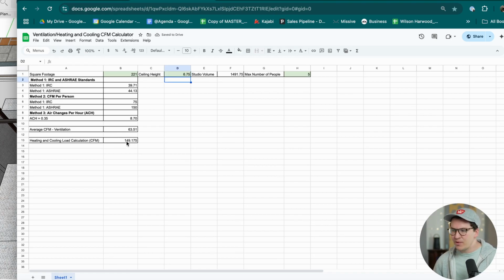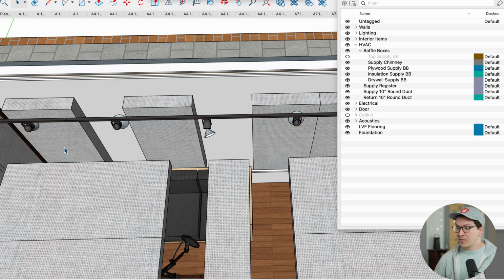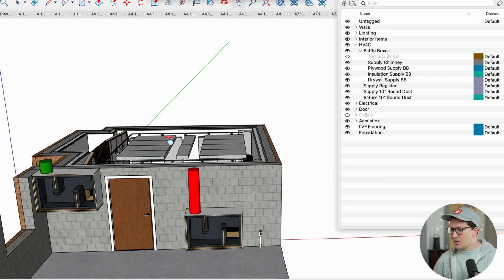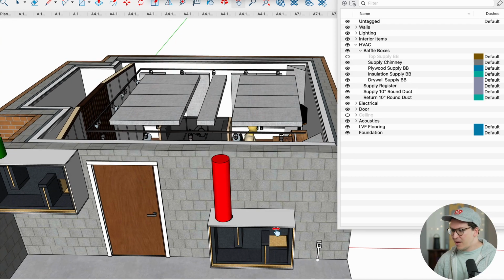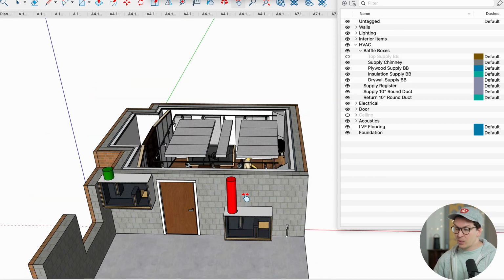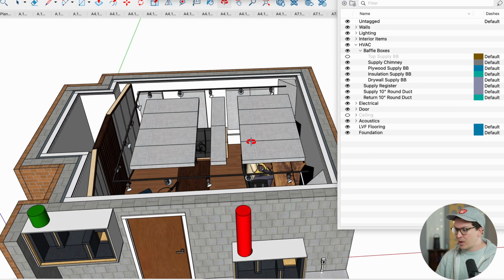We'll round it up to 150 CFM to properly heat and cool this room, and this will provide ventilation, because what's happening in here is that we're pulling from the air handler from the rest of the house. Now, it's not as good as having a dedicated ERV, but in this situation we're keeping things simple. We're just going to have the air coming through the air handler, which is pulling in air from other parts of the home. So we are getting some sort of air transfer and air exchange and ventilation in and out of this room, which is the important part.